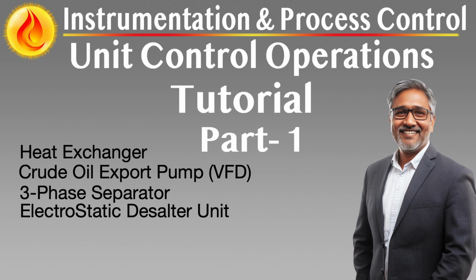Desalter control is also becoming increasingly integrated with upstream blending and downstream distillation control. In a model-based control framework, crude API, sulfur, salt content, and water cut are used to dynamically adjust desalter parameters to align with refinery corrosion targets and heat exchanger constraints. By coordinating desalter behavior with upstream blend predictions and downstream crude unit flexibility, the overall crude processing chain becomes more resilient and efficient. Looking forward, AI-powered desalter management systems are emerging.